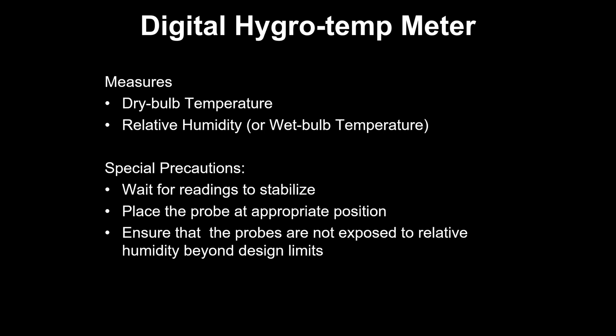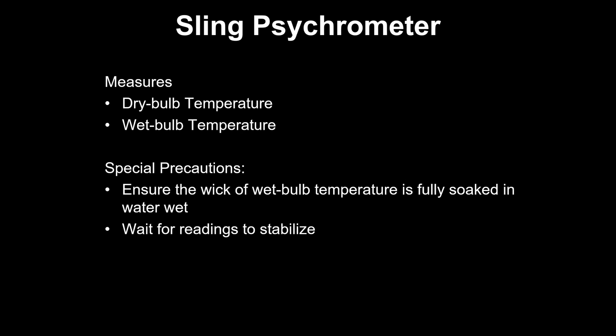We are still using it for cooling towers many times, because at the top of the cooling tower, when we are doing the exhaust air analysis, we use a sling psychrometer, for the same reason as I said: any hygrometer will get locked if the probe gets wet. These instruments normally say 100% non-condensing maximum, so any condensation means it will just get locked. It will not show the reading.